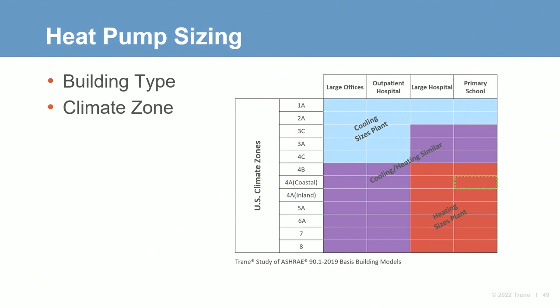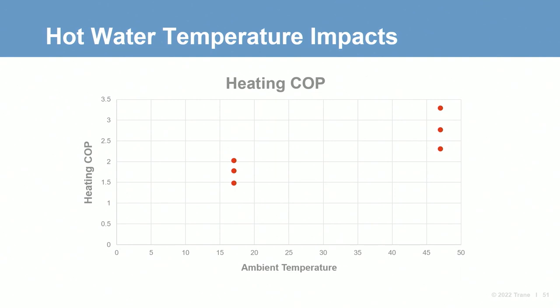requirements are closely matched. For the next section, we want to transition over to the design hot water set point used for these systems. The temperature the design team chooses to use will not impact the building required capacity. What will be impacted is the operating COP, or the efficiency of the heat pump, and its capacity. This graph is showing minimum efficiency requirements for air-to-water heat pumps in heating mode at standard AHRI heating conditions. There are three different supply hot water temperatures, 105, 120, and 140, at two different ambient conditions, 47 and 17 degrees.